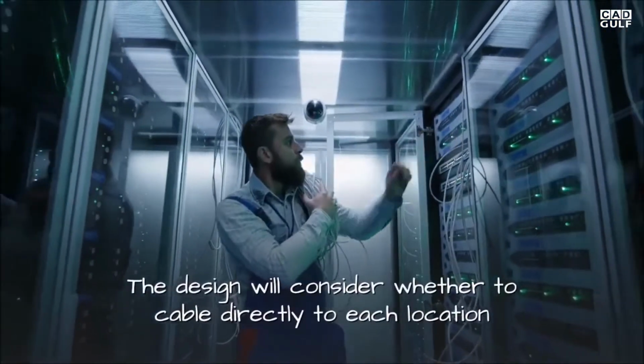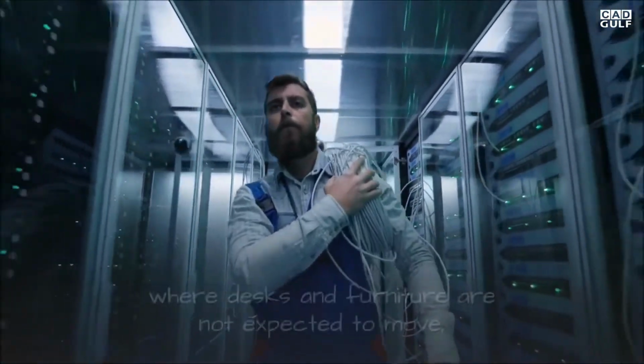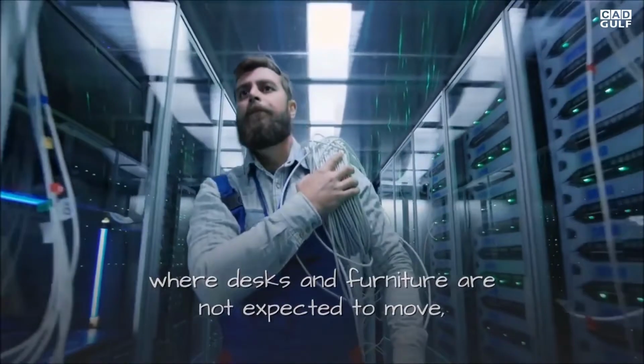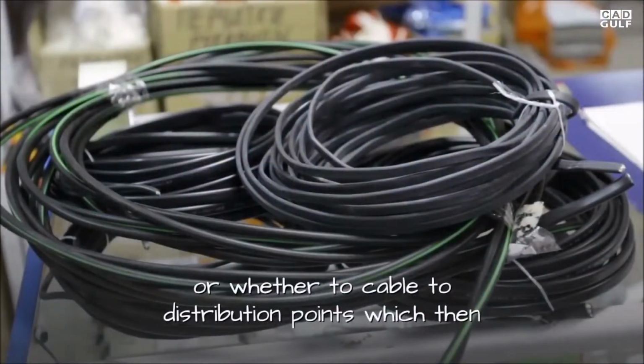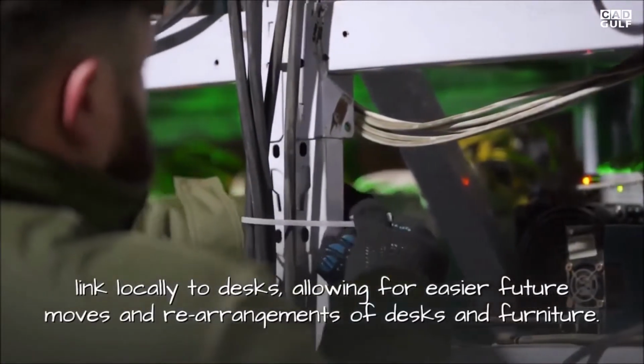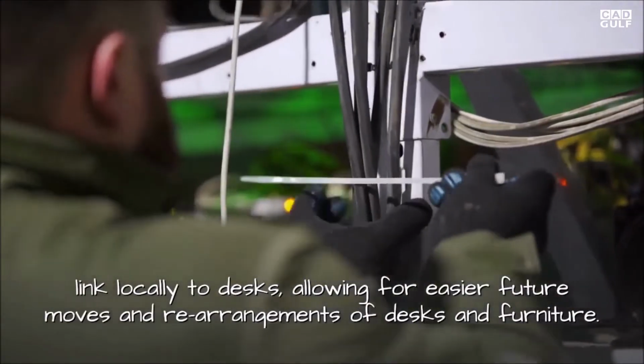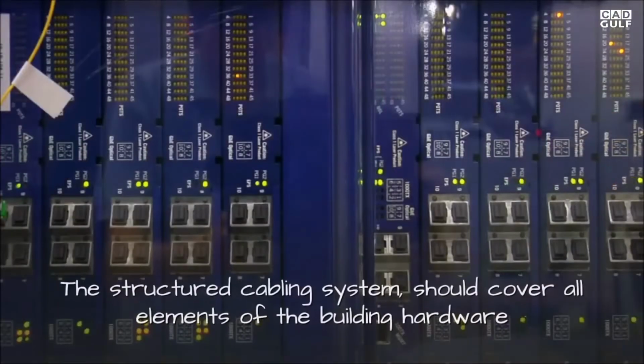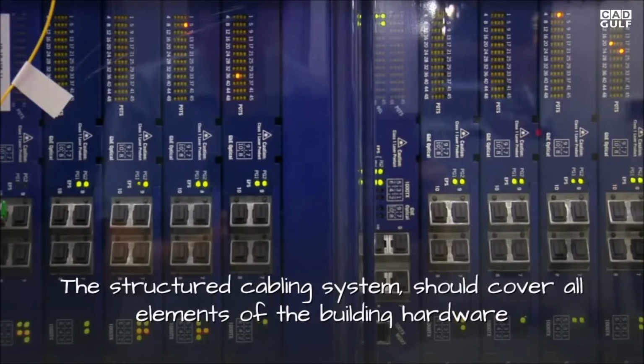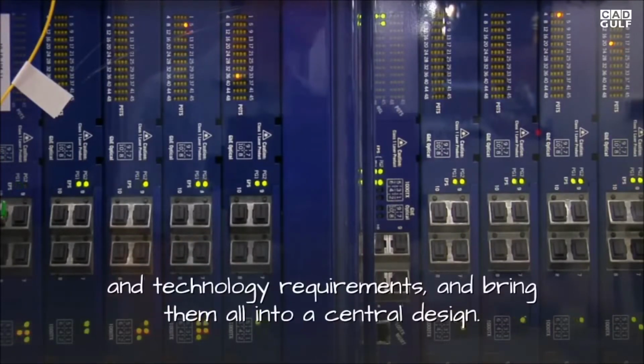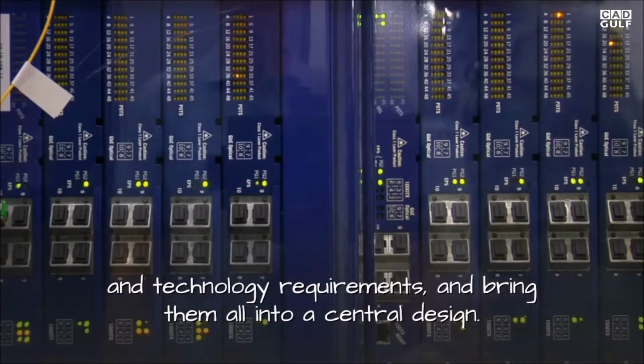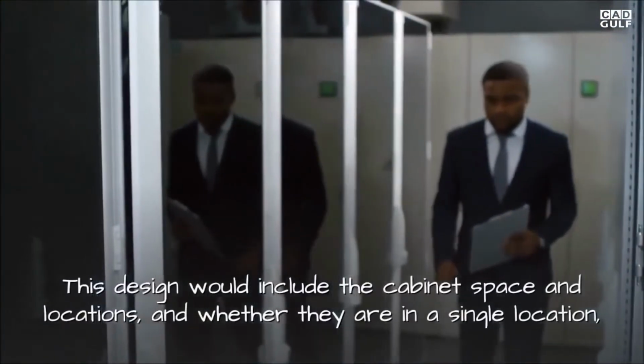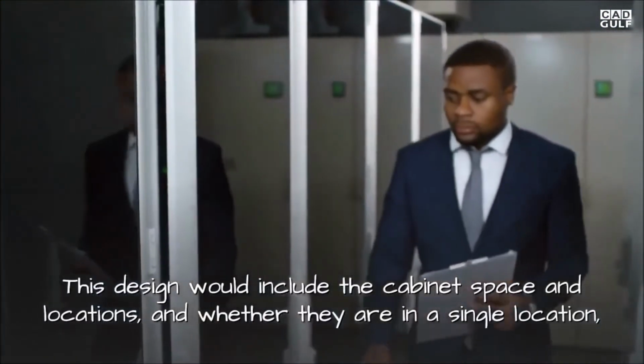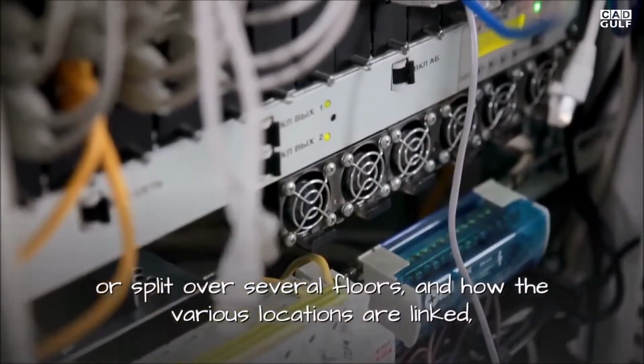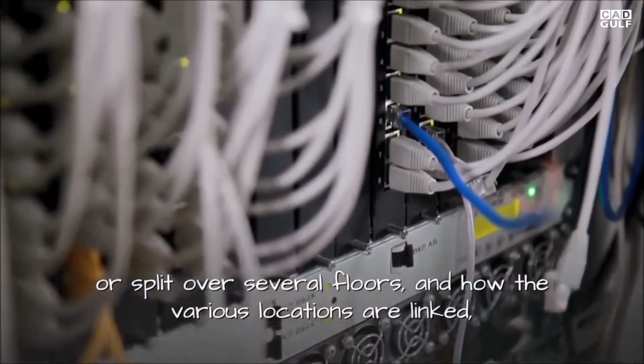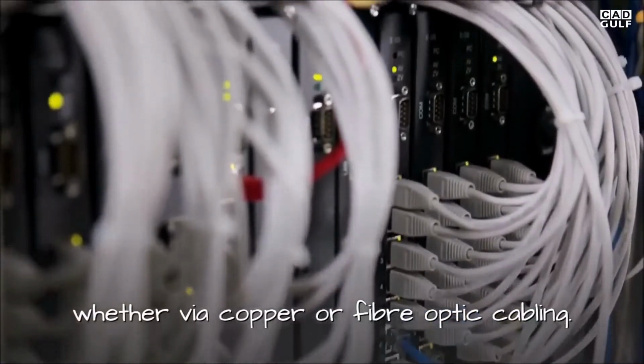The design will consider whether to cable directly to each location where desks and furniture are not expected to move, or whether to cable to distribution points which then link locally to desks, allowing for easier future moves and rearrangements of desks and furniture. The structured cabling system should cover all elements of the building hardware and technology requirements, and bring them all into a central design. This design would include the cabinet space and locations, and whether they are in a single location or split over several floors, and how the various locations are linked, whether via copper or fiber optic cabling.